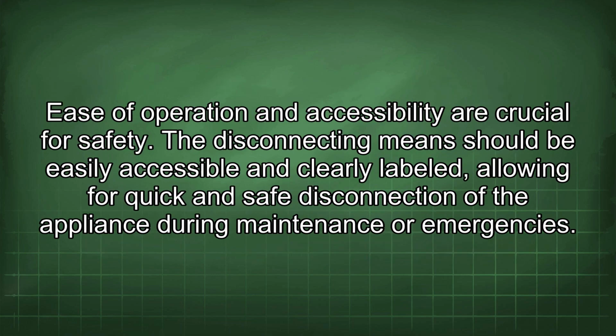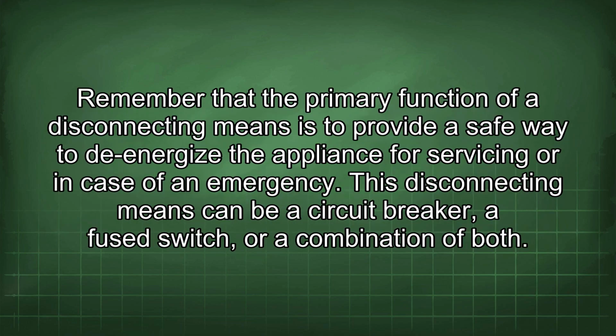Ease of operation and accessibility are crucial for safety. The disconnecting means should be easily accessible and clearly labeled, allowing for quick and safe disconnection of the appliance during maintenance or emergencies. Remember that the primary function of a disconnecting means is to provide a safe way to de-energize the appliance for servicing or in case of an emergency. This disconnecting means can be a circuit breaker, a fused switch, or a combination of both.